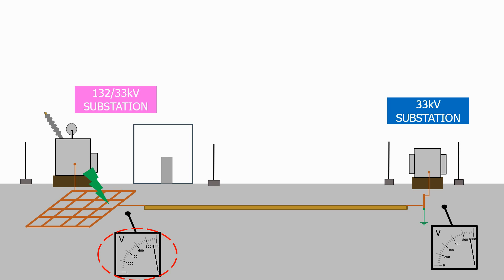The cable sheath is grounded to the 132 to 33kV substation, but also to the 33kV substation. As the cable sheath is connected to both grounding systems, the voltage potential of the ground grid below the 33kV substation will also increase to 960 volts — as will anything connected to the grounding grid, including the switchgear and transformers.